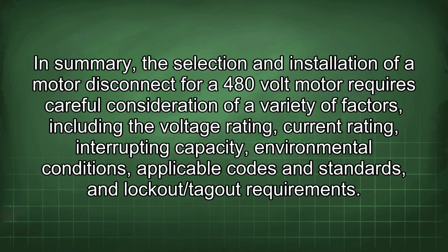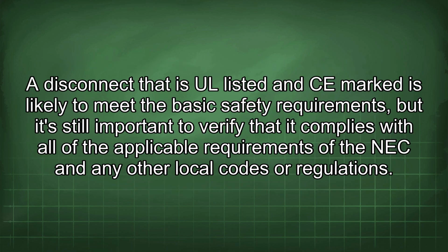In summary, the selection and installation of a motor disconnect for a 480-volt motor requires careful consideration of a variety of factors, including the voltage rating, current rating, interrupting capacity, environmental conditions, applicable codes and standards, and lockout/tagout requirements.